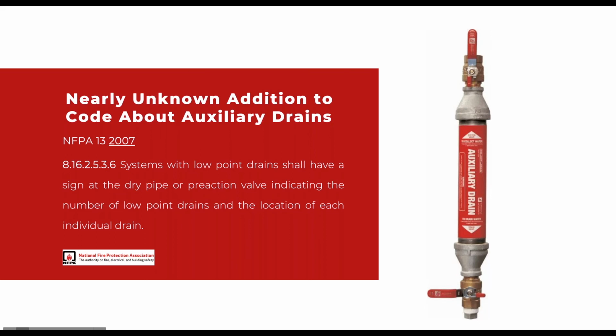And one of the unique things, and this is something that was an issue in Texas, just because they were surprised, there is a requirement that if you have a dry or a pre-action system in your building, on the general information sign that is located at each of your dry valves, there is supposed to be some indication of the quantity and location of each of these low point drains. Because in the event someone doesn't know where one of these is located in the building, and then that building is subjected to some very brief amount of freezing temperatures, that accumulated moisture may freeze and crack, and then it releases the air that's under pressure in the system, and water comes rushing in, or you could have a catastrophic issue where the system freezes and breaks and causes extensive water damage.